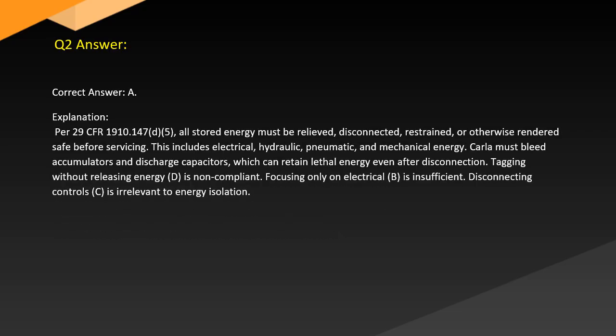Answer. Correct answer: A. Explanation. Per 29 CFR 1910.147 D5, all stored energy must be relieved, disconnected, restrained, or otherwise rendered safe before servicing. This includes electrical, hydraulic, pneumatic, and mechanical energy. Carla must bleed accumulators and discharge capacitors, which can retain lethal energy even after disconnection. Tagging without releasing energy, D, is non-compliant. Focusing only on electrical, B, is insufficient. Disconnecting controls, C, is irrelevant to energy isolation.